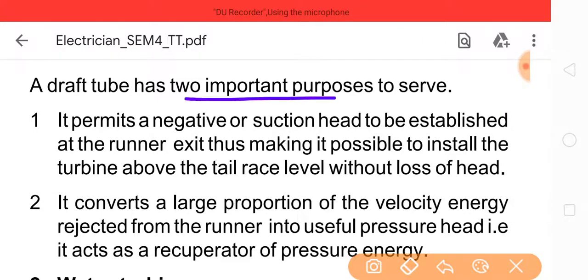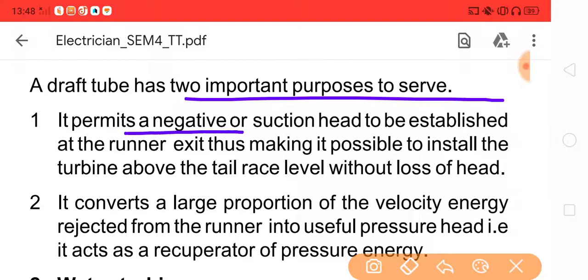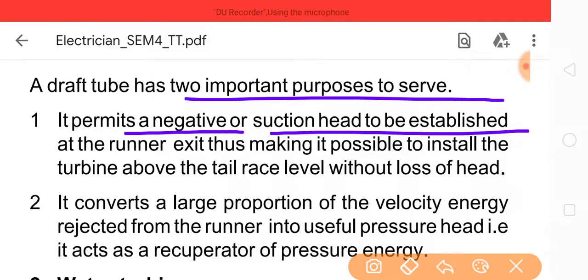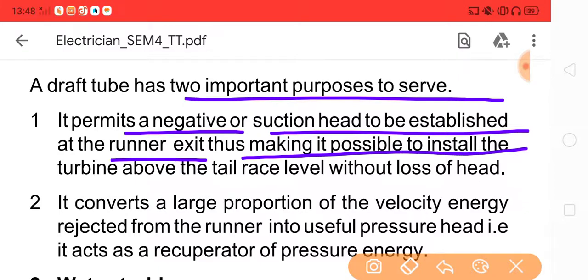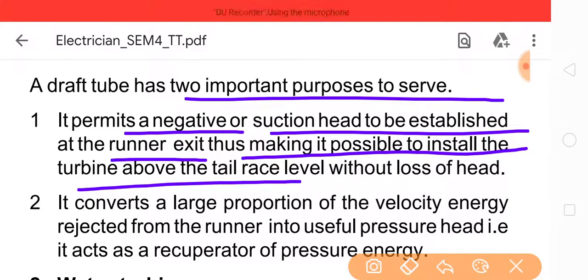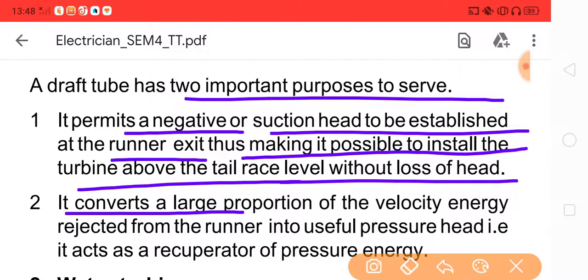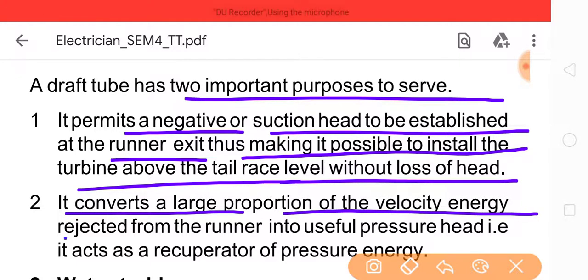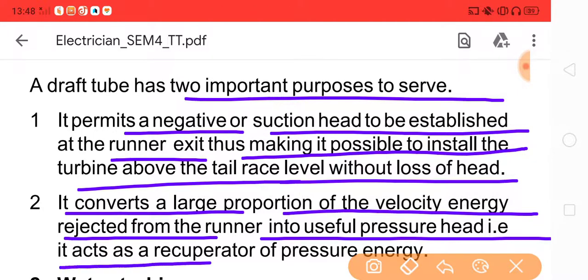draft tube has two important purposes to serve. It permits a negative or suction head to be established at the runner exit, thus making it possible to install the turbine above the tail race level without loss of head. It converts a large portion of the velocity energy rejected from the runner into useful pressure head. It acts as a recuperator of pressure energy.